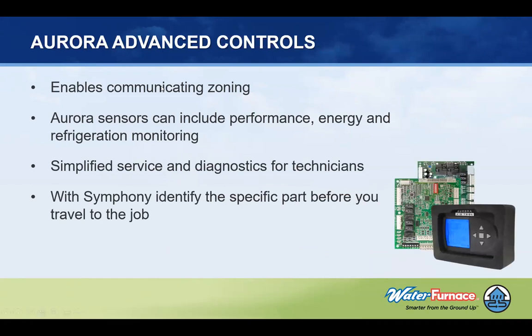So it enables the zoning that we talked about, which gives us the ability to control by zone. We also have sensors that do performance, energy, and refrigeration. That makes the service significantly simplified for the technician to diagnose a problem. And we can nine times out of ten identify the specific part that has failed before we ever travel to the job.